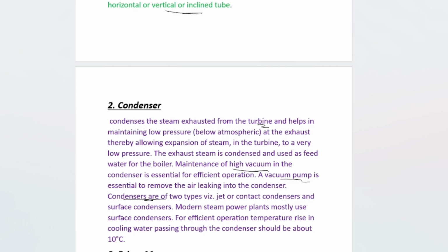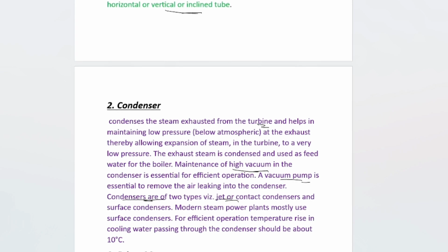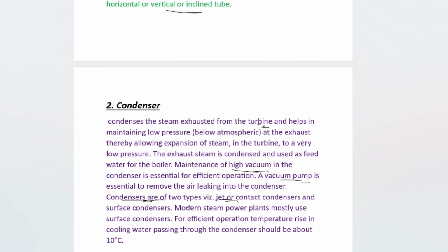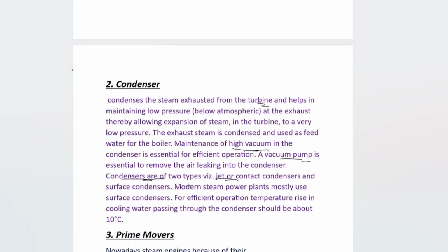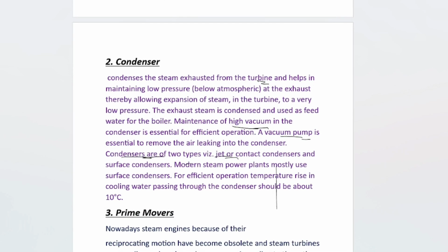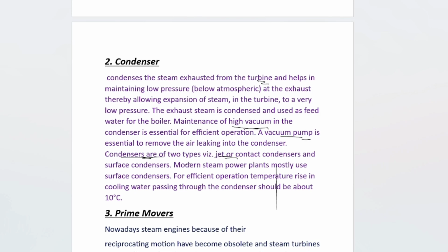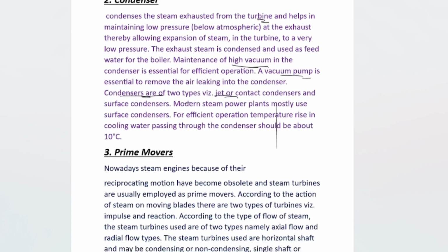Condensers are of two types: jet or contact condensers, and surface condensers. Modern steam power plants mostly use surface condensers. For the most efficient operation, the temperature rise in the cooling water passing through the condenser should be about 10 degrees Celsius.